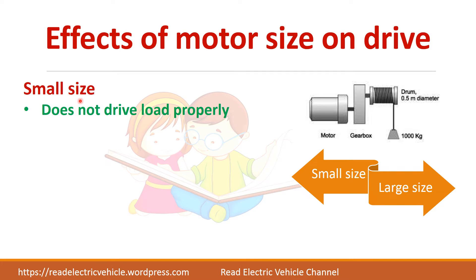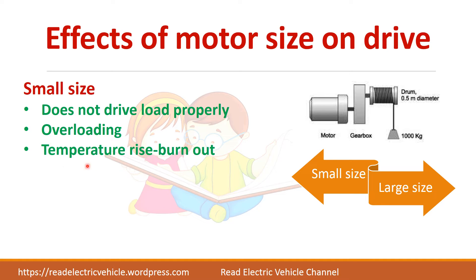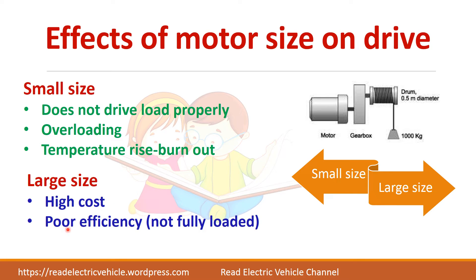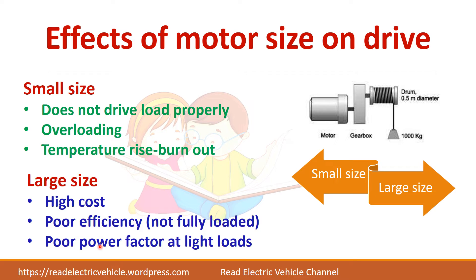If you choose a small size motor, there is a possibility that it may not drive the load properly because it will not have that capacity. Overloading of the motor may occur, which will increase the temperature of the motor. And if you choose a large size, cost will increase. Apart from that, the efficiency will be very poor because the motor is not fully loaded, and in AC machines it may lead to poor power factor at light loads.